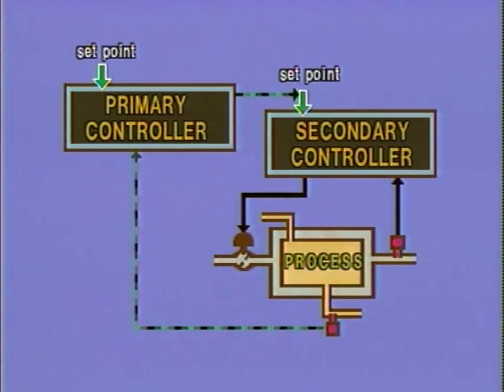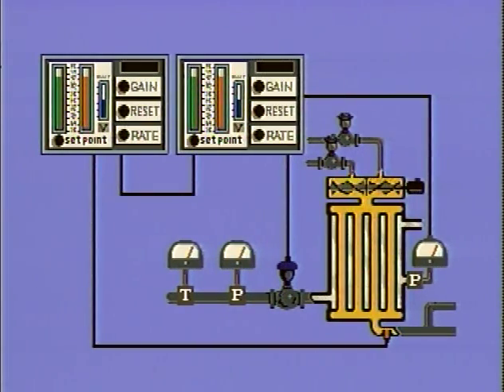Here is how the chemical company used cascade control to keep the product temperature closer to the set point. The steam pressure in the heat exchanger shell was monitored, since it rose or fell almost immediately if there was a change in the steam supply. The output of this pressure sensor went to a controller that caused the steam valve to open or close in proportion to the shell pressure. This was the inner or secondary feedback loop.